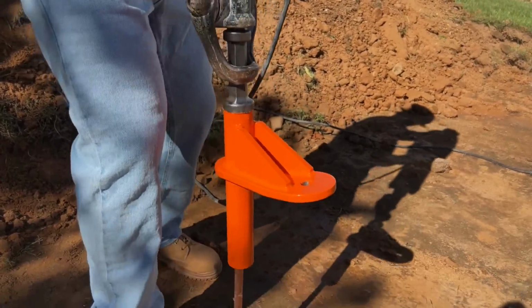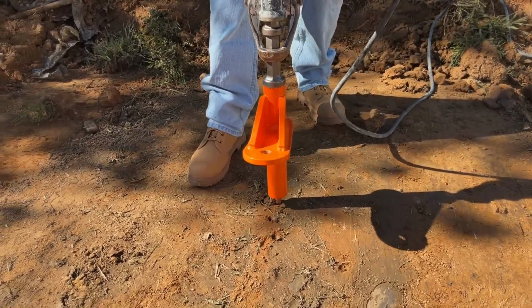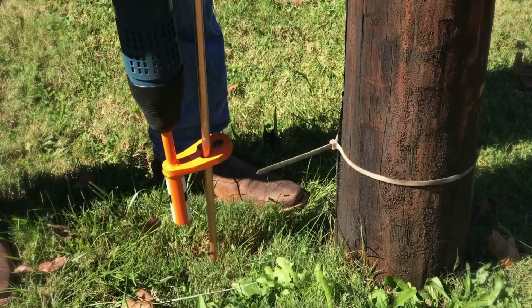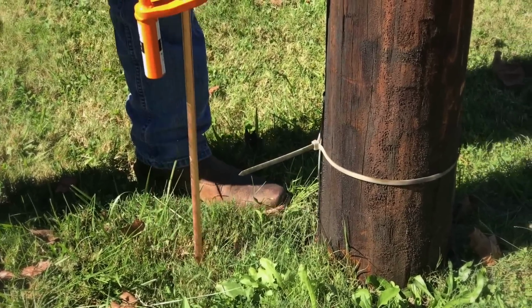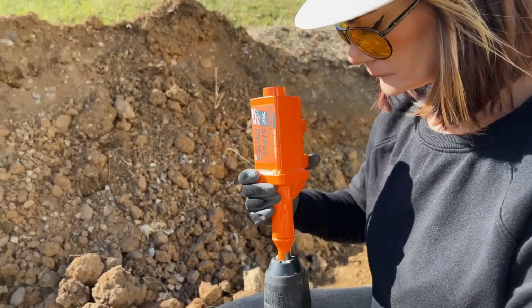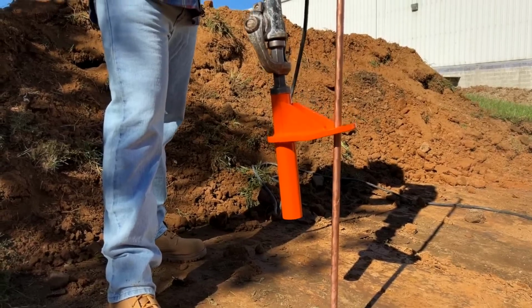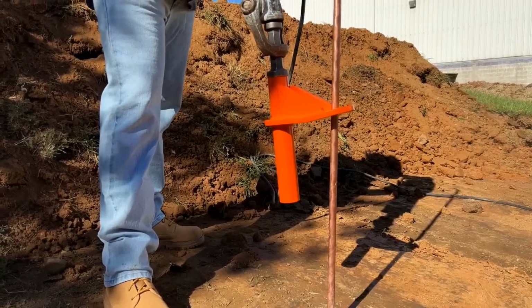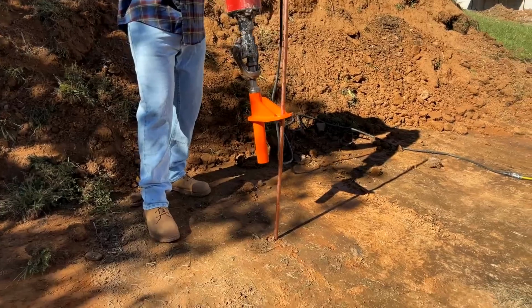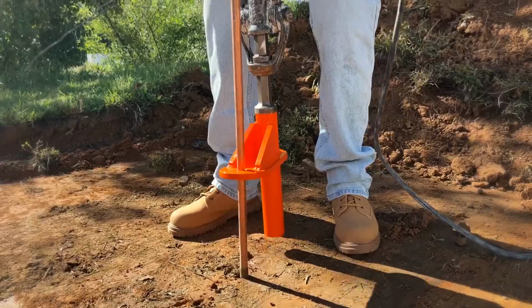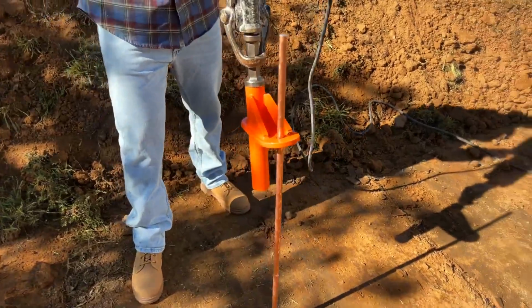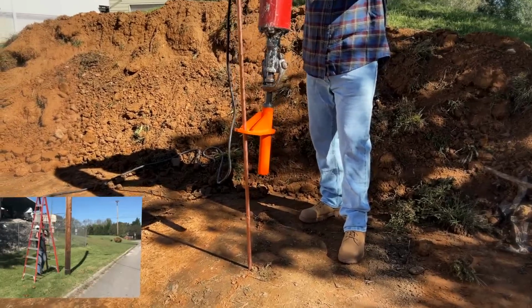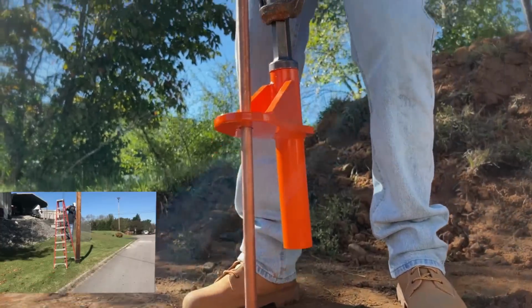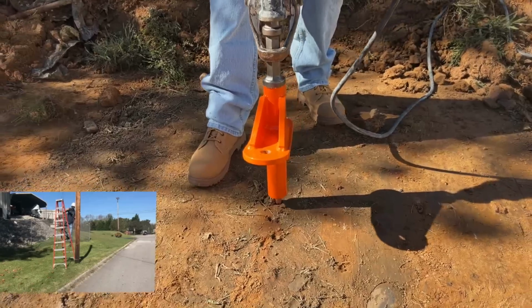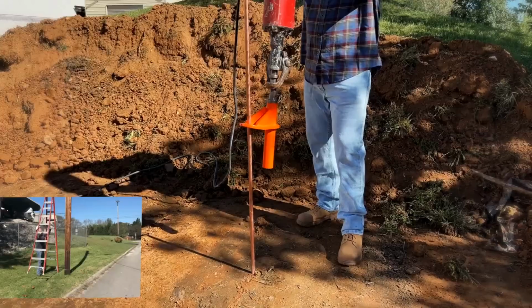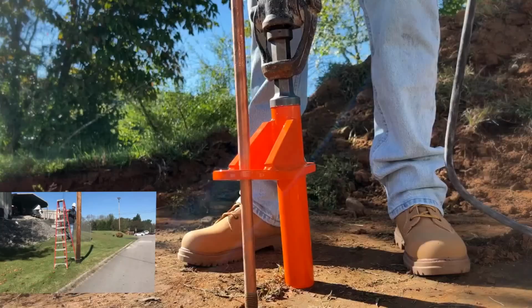Next, locate a suitable area for the ground rod. This should be an area with good drainage and minimal vegetation, as the ground rod will need to be driven into the ground. Keep the drill running and continue to lower the Ground Rod Dawg XL until the ground rod is fully installed. This may take several minutes, depending on the soil conditions and the size of the ground rod. Once the ground rod is fully installed, stop the drill and remove the Ground Rod Dawg XL from the ground. The ground rod is now ready to be used for grounding electrical systems or other applications.